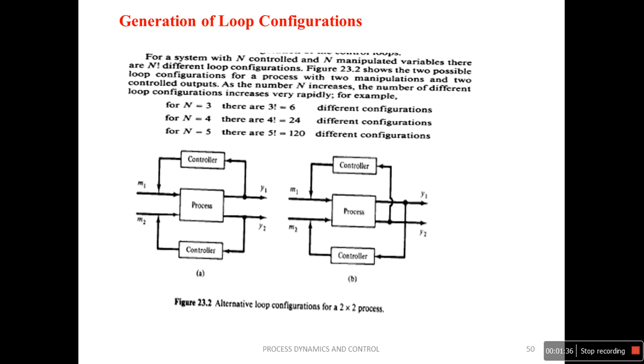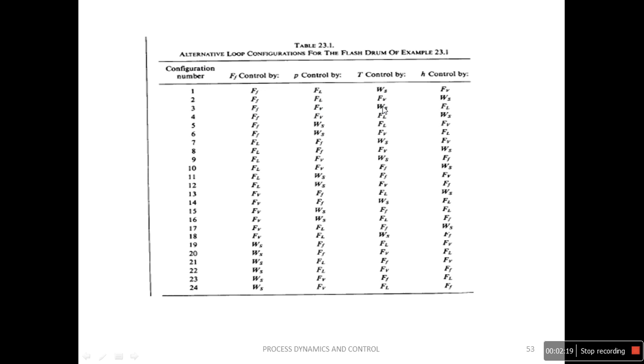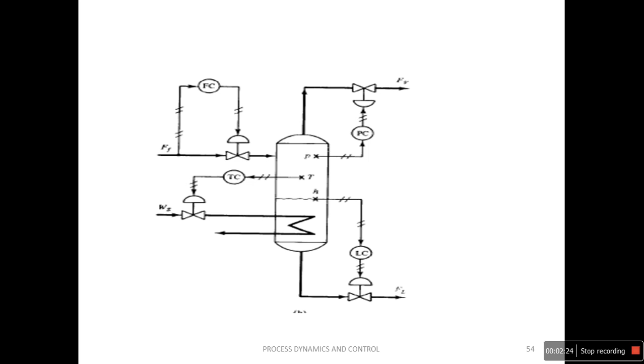In the last class we discussed the small flash drum control, where we took four control variables: the pressure, temperature, feed flow rate and level of the drum. Here we may have 4 factorial, that is 24, control configurations, which we have already discussed. Among them we selected the third configuration, where the feed flow rate is controlled by manipulating the feed flow only, the pressure is controlled by manipulating the flow of the vapor, the temperature is controlled by the steam flow rate, and the level is controlled by the outflow of the liquid.